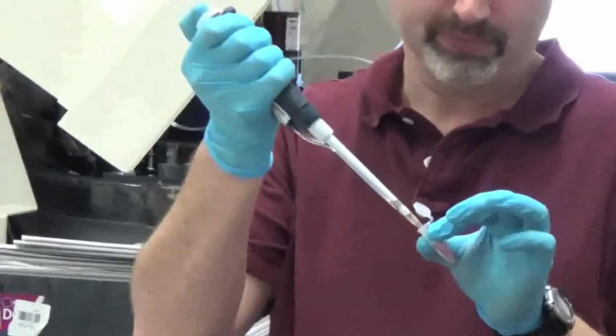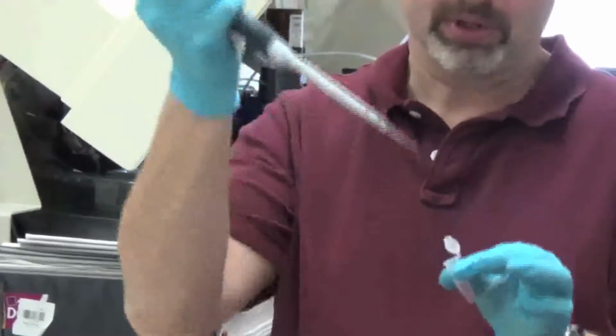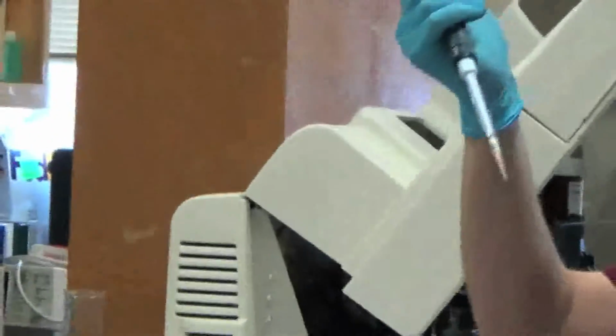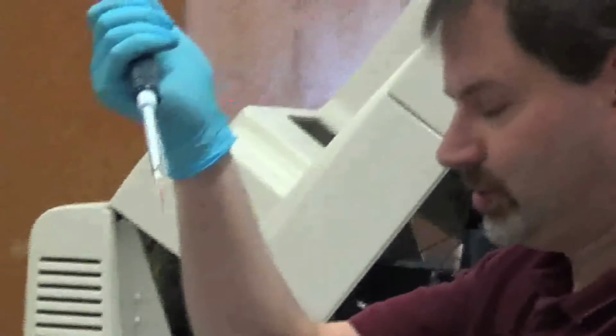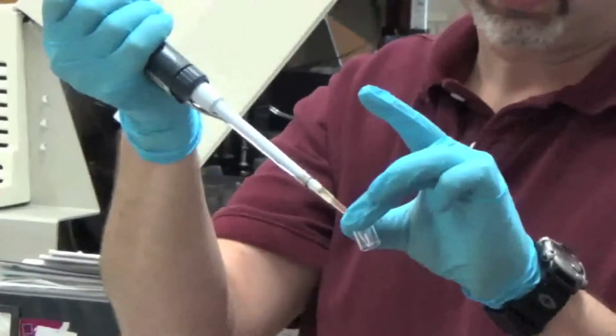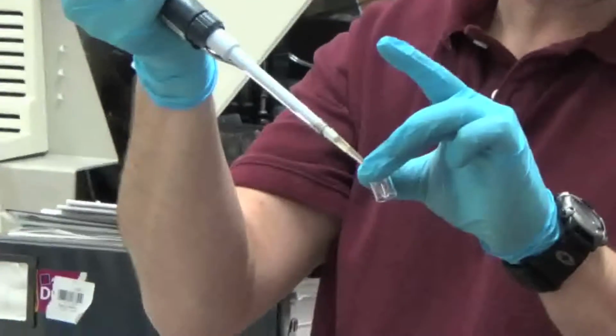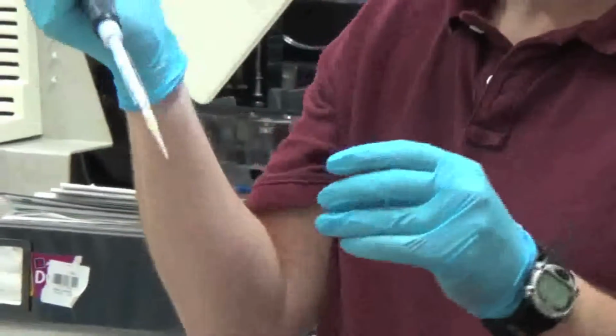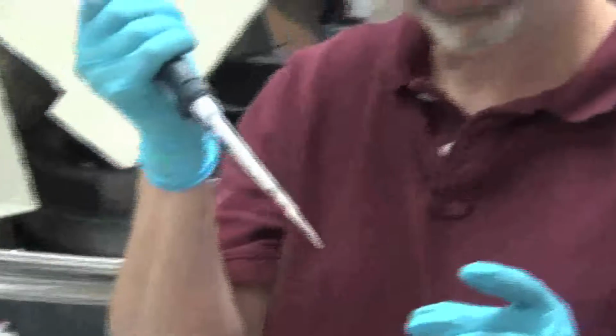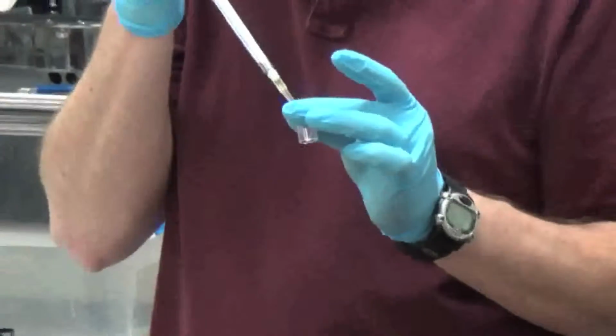I'm now going to remove 160 microliters of this serum from this tube so that it is now in the pipette tip, and then place it into my vessel, which is a sample collection system. It's very important for this specific machine never to have a bubble at the top of your sample. So I now have a little bubble because I ejected it completely. I removed the bubble by sucking it back out, and it's now bubble free.